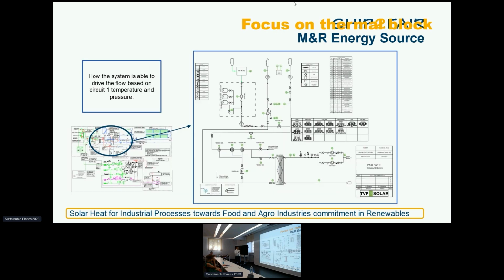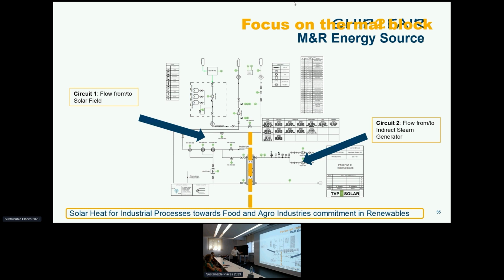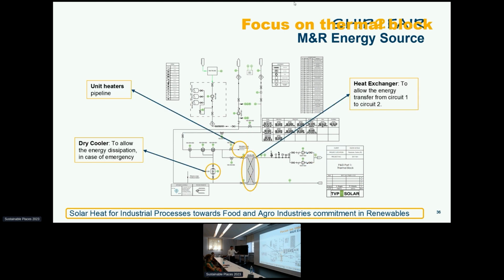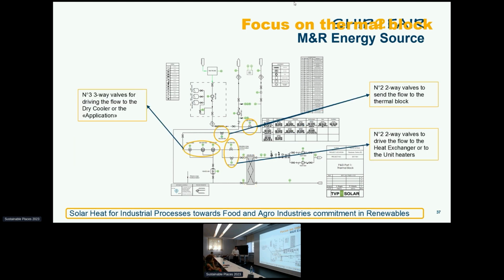Just a quick overview of the thermal block, which is the main side of the system responsible for driving the flow properly. Here we can see the border separating circuit 1 from circuit 2, and the main equipment installed, starting with the applications: the unit heaters for the winter mode and the heat exchanger for the summer mode. And the dry cooler, which is crucial equipment for dissipating the excess of energy in case of emergency or failure, or once the temperature increases above a certain limit. The flow is driven properly thanks to these groups of two-way and three-way valves, all connected with the PLC and driven by the irradiation, temperature, and pressure of circuit 1.